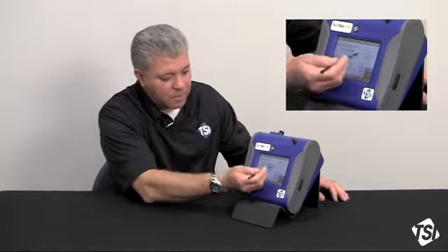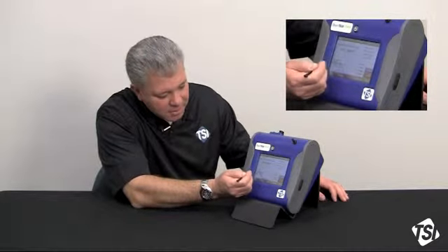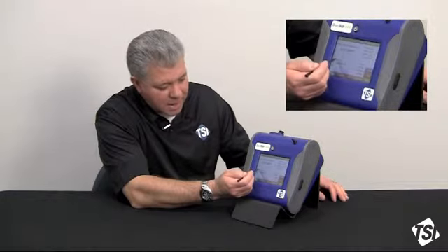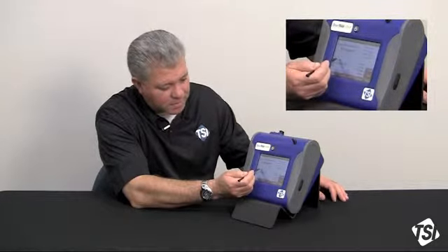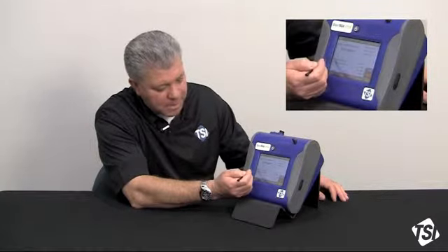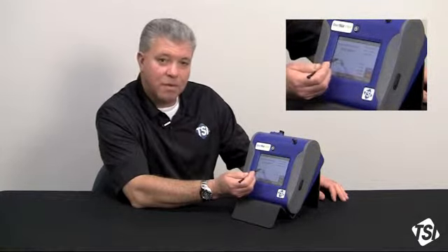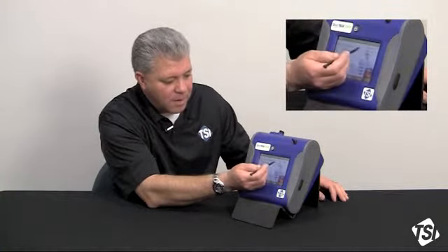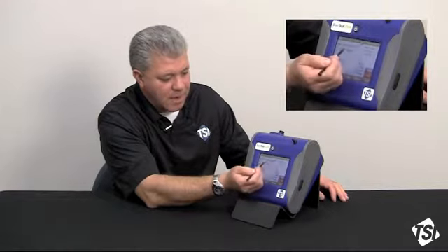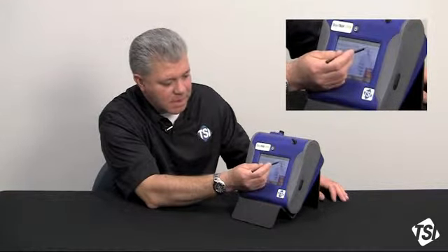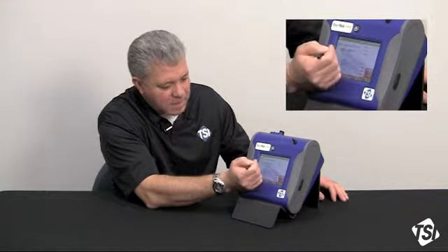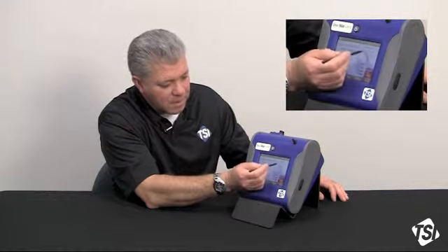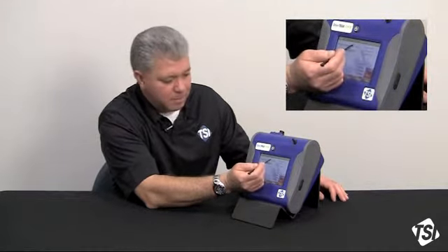Now, if you look at all 5 size fractions and come over here, it indicates that all sizes are being looked at. If I touch this area right here, it's another live key, I can toggle that to be an indoor air quality, outdoor environmental size, and what we're looking at now is PM1, total, PM10, and PM2.5. Let's say I want to see PM2.5 as my size fraction. I come up and they realign themselves again. PM2.5 here, total, PM10, and PM1.